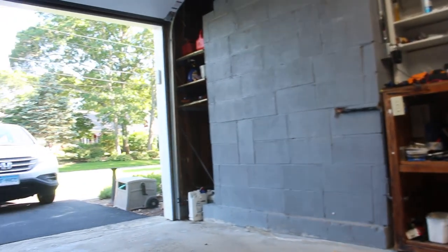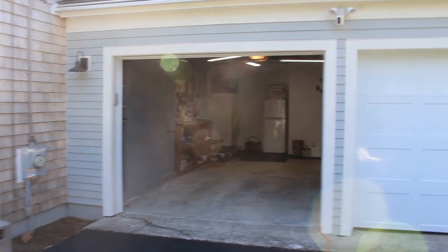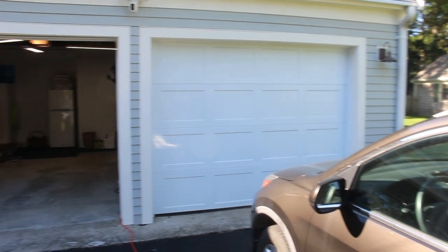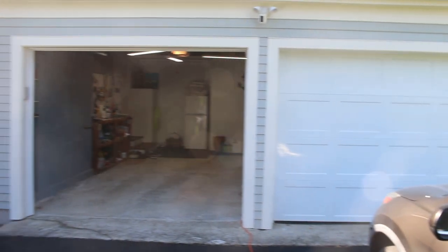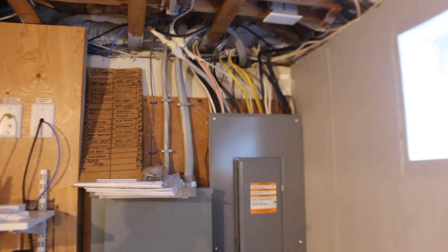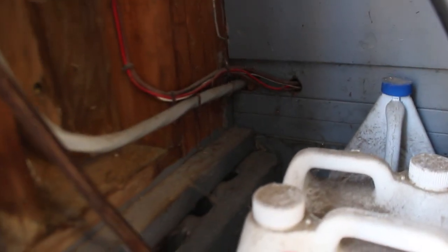In this demonstration our setup includes a garage with two car bays and a driveway that fits two cars side by side. You might have a different parking situation but this example will apply to any home. Our electrical panel is located in the basement and has 200 amp service running from the street into the house. Luckily the electrical panel is mounted directly on the other side of the wall to the garage so the run of wires from the panel will be relatively short.